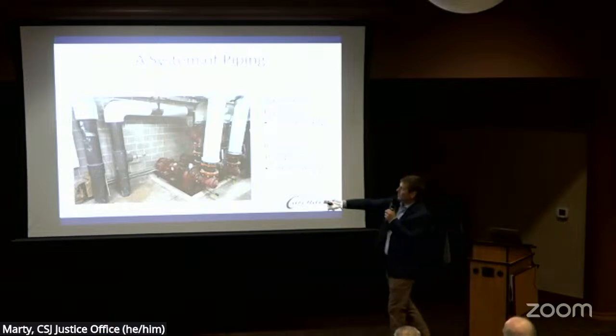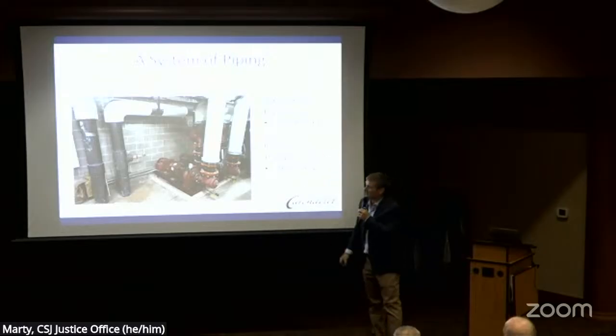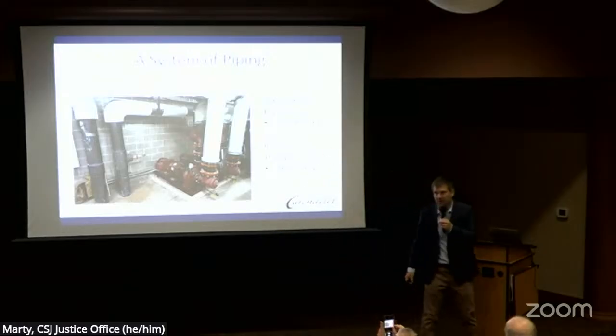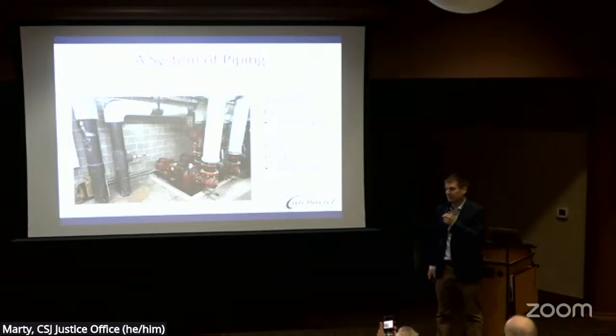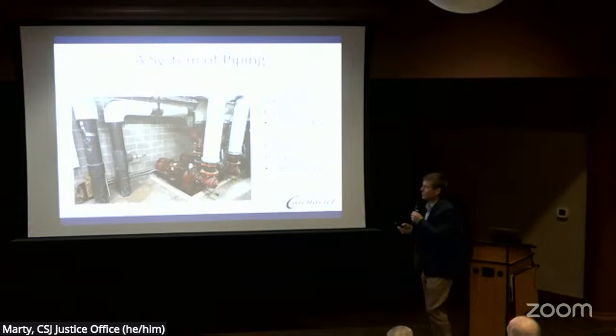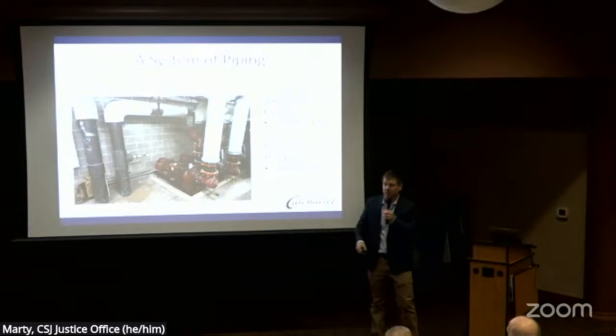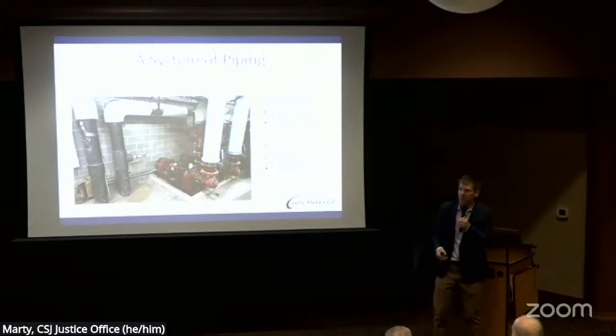And their whole job is to keep all of this mixed up and moving around. So the well field pumps, these first 2, are set to pump 1,100 gallons per minute at max capacity. If you think about that, if we had a 1-gallon jug of water in here, 1,100 gallon jugs would fill this room pretty well. That's getting pumped every minute throughout that system, out to the field and back. Once it's done there, then we send it over to the other set of pumps, and they're able to pump 900 gallons per minute out into the building.